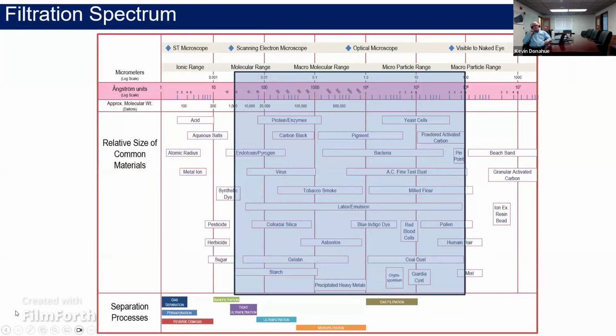So first things first, some of you may be familiar with membrane filtration already. This is just a display to show the range of separation capabilities with membrane filtration. One thing I want to make note of is that ceramic membranes are used only in the range between nanofiltration and microfiltration. Today, there exist no reverse osmosis ceramic membranes. That's I would say the new frontier for the technology. So, for the foreseeable future, we're just talking about nanofiltration, ultrafiltration, and microfiltration membranes. Next slide, please.